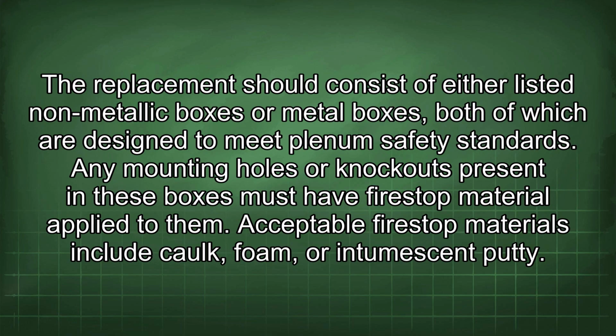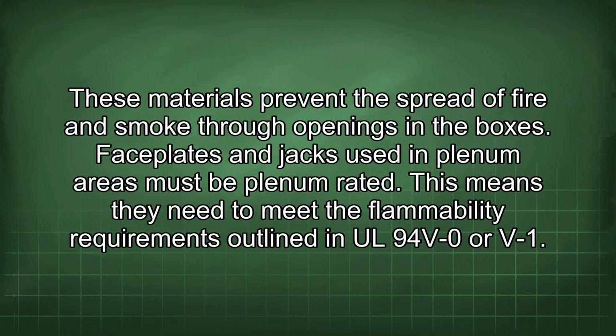The replacement should consist of either listed non-metallic boxes or metal boxes, both of which are designed to meet plenum safety standards. Any mounting holes or knockouts present in these boxes must have Firestop material applied to them. Acceptable Firestop materials include caulk, foam, or intumescent putty. These materials prevent the spread of fire and smoke through openings in the boxes.